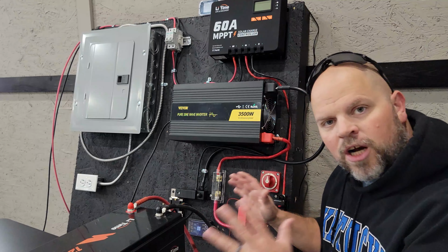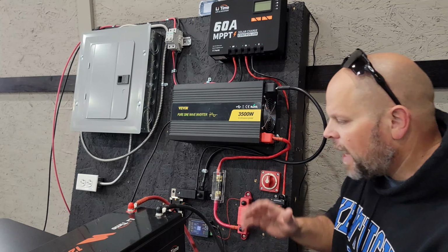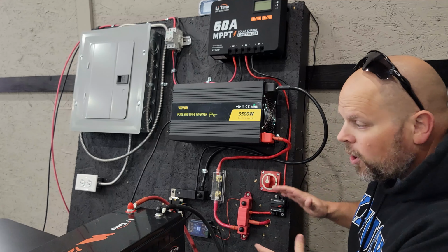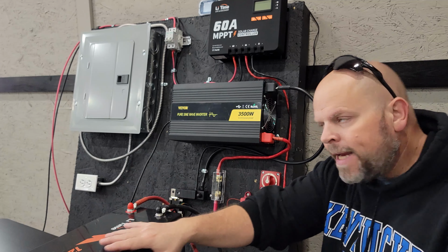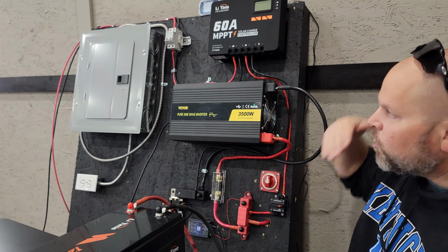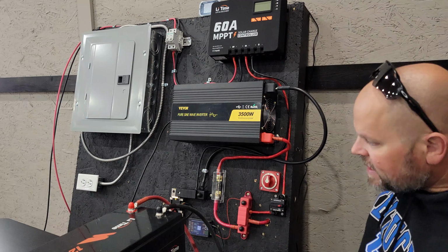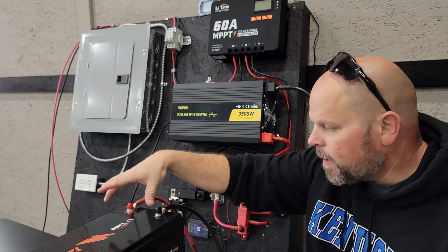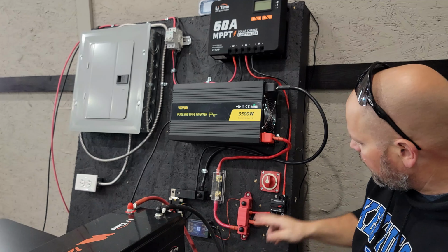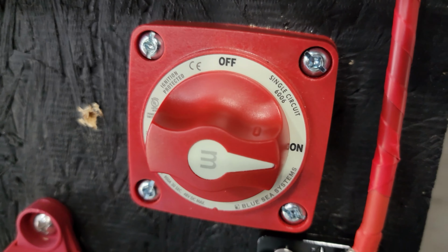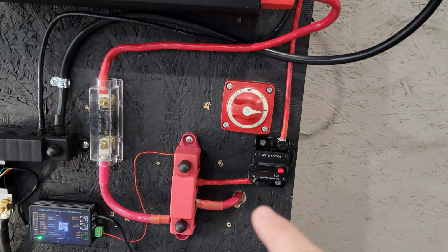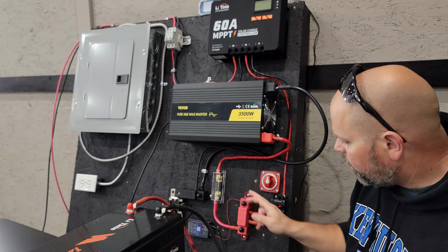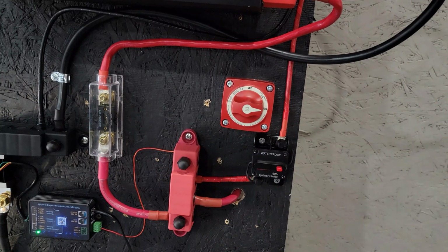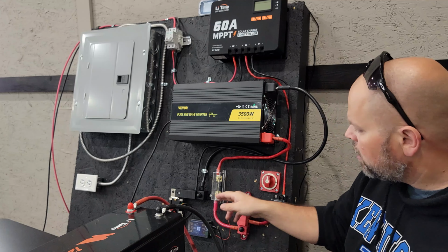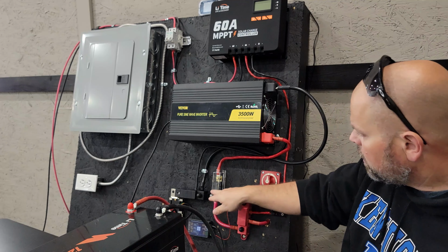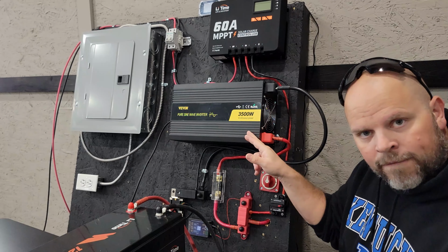Before I start testing, I think it's important to explain what I've got going on here. We'll start from the battery up to the inverter, then talk about the MPPT down to the battery. From the battery, we have our positive line coming into this switch, which feeds this bar, that comes over to this fuse, appropriately sized—you'll have to figure that out for your system—and then it comes up to our inverter.